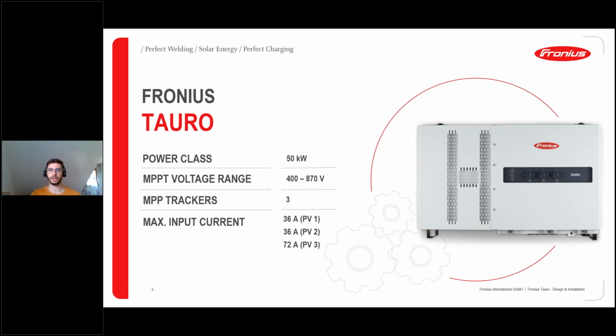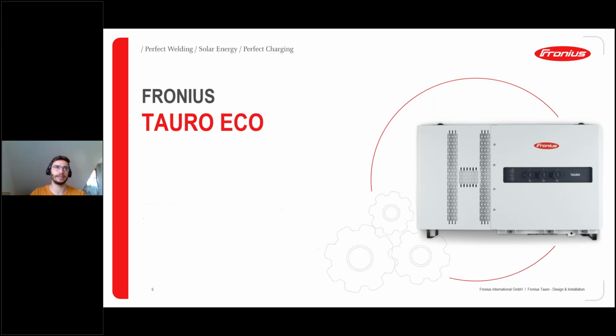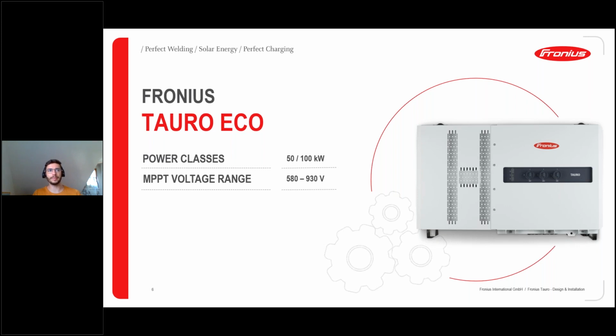This is the Fronius Tauro, which will come in a few weeks. The Fronius Tauro ECO is already in production. It's available in power classes 50 and 100 kilowatt, so a bit bigger, with a more limited voltage range of 580 to 930 volts and 1 MPP tracker. That's one of the main differences between the two products: 3 versus 1 MPP trackers. For input current, the 50 kilowatt device has 87.5 amps, and the 100 kilowatt device has 175 amps.